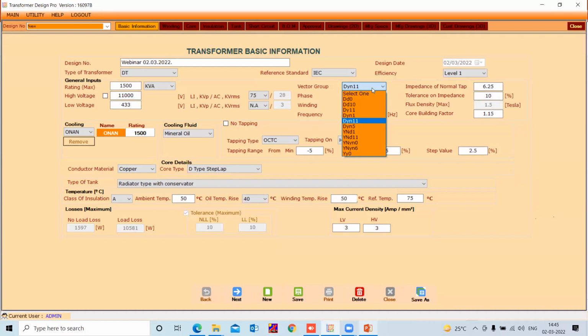Okay, you can select the vector group. You can choose any one. It's 3-phase, 50 Hertz, 60 Hertz, both options are there for the frequencies. You can go for the impedance at normal tap. Whatever you see in the white background is all editable. You can write whatever you wish to write. The tolerance depends upon the standard, the reference standard. The moment you go for a different reference standard, the tolerance on impedance possibly will vary. Similarly, the flux density is editable.